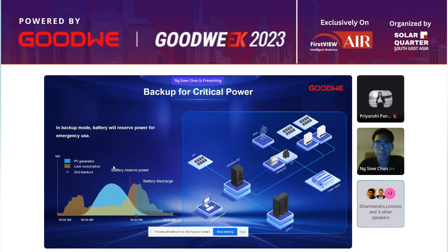Last but not least, backup mode. Besides grid operation, our battery energy storage systems are able to support backup function during power outages. We are very proud to announce that we are able to do UPS level switching, meaning during a power outage, our battery system will switch into backup mode within 10 milliseconds. We can charge our batteries during peak hours or excess power, and even have a capacity reserve in the batteries so that during an outage, it can discharge and support local loads, giving a 24/7 power supply even during grid blackout.